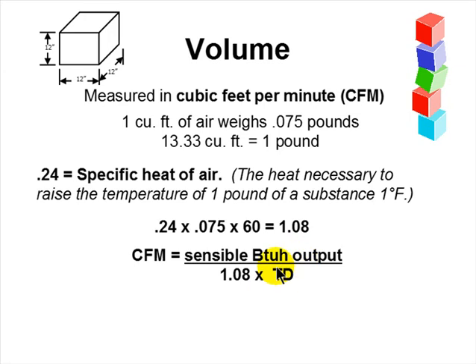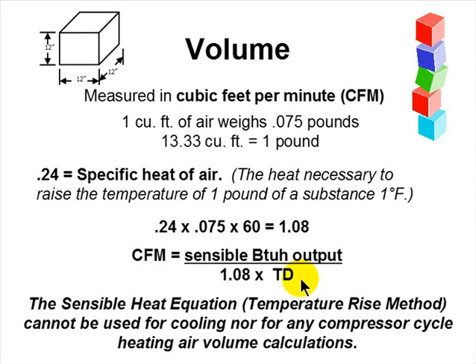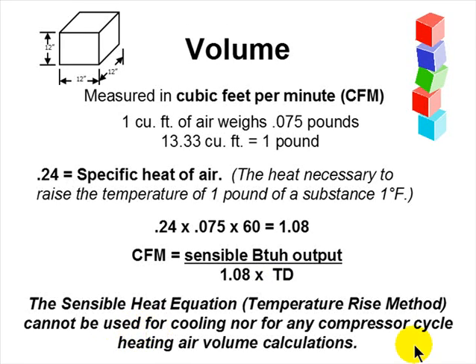To be correct, the temperature difference should be the difference between the air temperature in the duct and the air temperature in the room you're supplying it to — very often they work out to be similar. The sensible heat equation — the temperature rise method of determining volume — cannot be used for cooling, nor for any vapor compression cycle heating air volume calculation, because we need to separate sensible heat from latent heat.